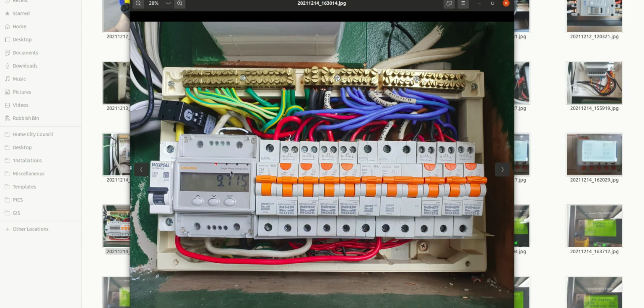So this one here is downstream from this kilowatt hour meter here, so it doesn't get confused. This kilowatt hour meter, the retro one from 2017, will get confused if it's perhaps exporting back to the grid more power than the inverter it's connected to, and it'll go into fault mode. So that's downstream, independent, and this one can recognize that there's possibly another grid connect inverter there. So that one went upstream from this one and also separate. It's in parallel. As you can see, this red wire goes across to the Alpha ESS, and this one here does whatever it likes, because being downstream. I'm repeating myself, but it's good to reinforce it.